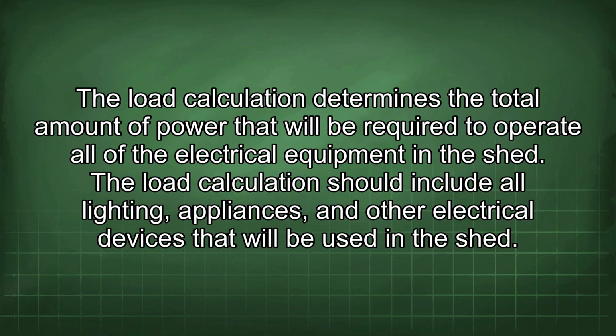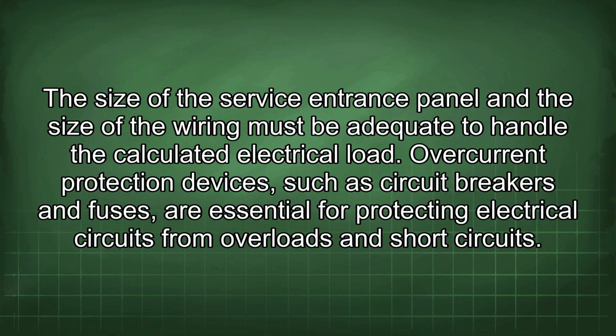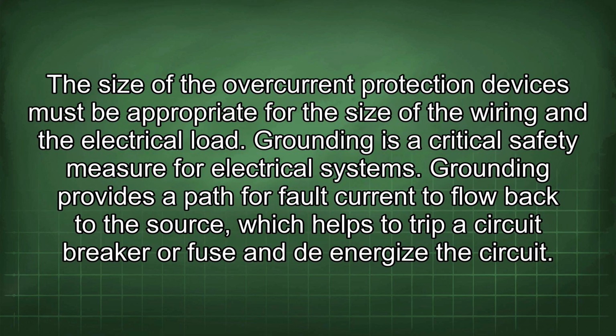The load calculation determines the total amount of power that will be required to operate all of the electrical equipment in the shed. The load calculation should include all lighting, appliances, and other electrical devices that will be used in the shed. The size of the service entrance panel and the size of the wiring must be adequate to handle the calculated electrical load. Overcurrent protection devices, such as circuit breakers and fuses, are essential for protecting electrical circuits from overloads and short circuits. The size of the overcurrent protection devices must be appropriate for the size of the wiring and the electrical load.